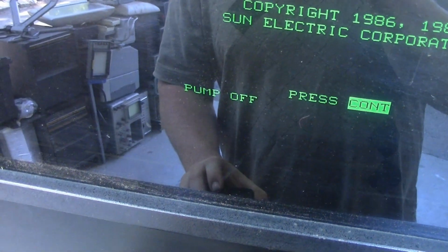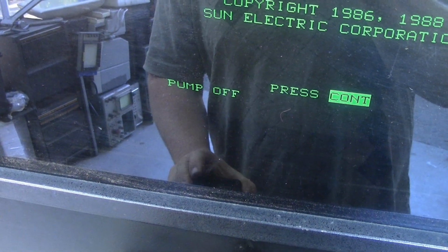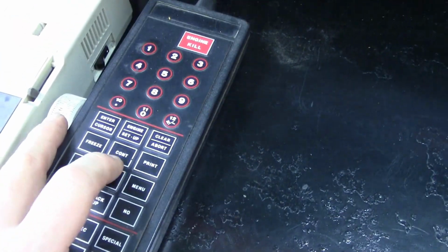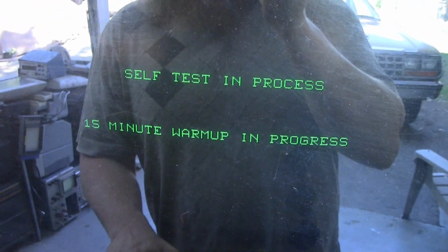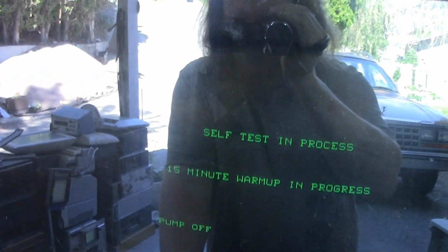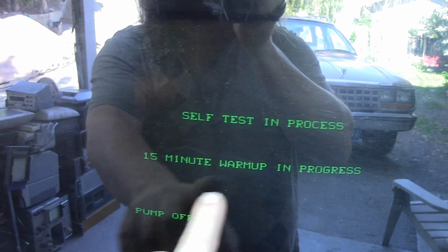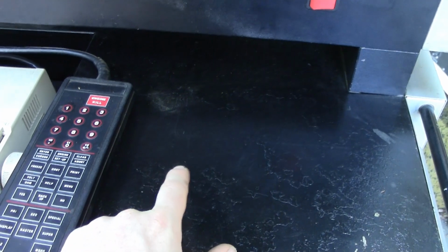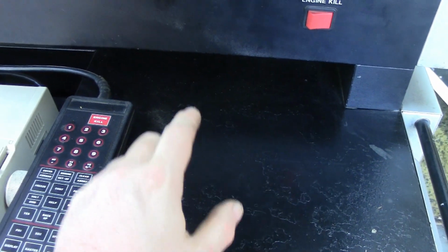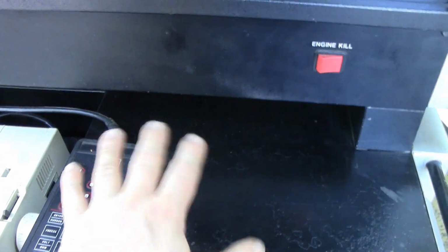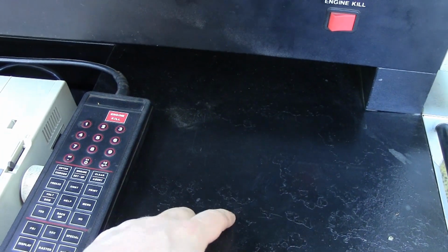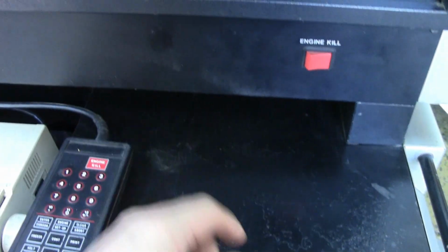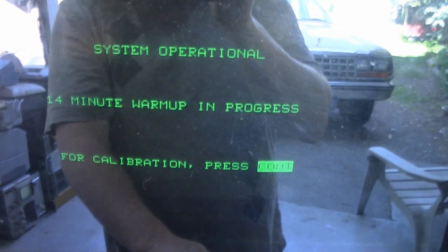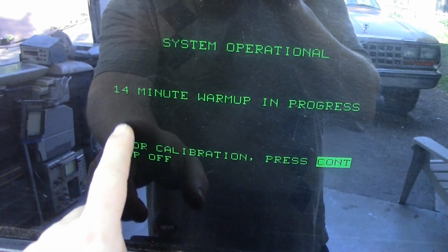Pump off indicates that the switch for the gas analyzer is currently off. So I'm going to hit the continue button here, and it'll go through a self-test procedure. The self-test procedures pretty much just make sure that electronically everything is good. It also says here 15-minute warm-up in progress. The gas analyzer is not ready to work immediately. It requires a warm-up cycle before it's ready to calibrate itself. You can do other things with the analyzer, but the gas analyzer won't be reliable, or I don't even think will work until after it's finished 15 minutes. So there we go. And even in the time I've talked to you, it's already down to 14.